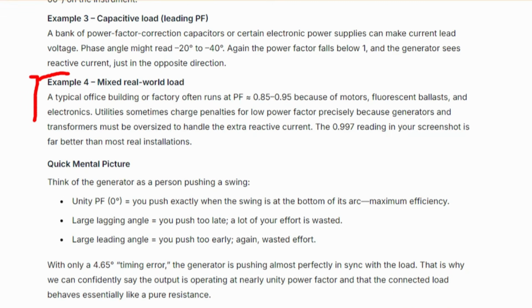Example 4, mixed real-world load. A typical office building or factory often runs at a power factor of approximately 0.85 to 0.95 because of motors, fluorescent ballasts, and electronics. Utilities sometimes charge penalties for low power factor, precisely because generators and transformers must be oversized to handle the extra reactive current. A 0.997 reading on your screenshot is far better than most real installations.